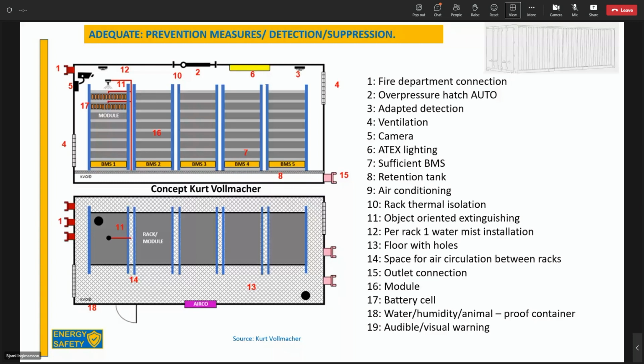The presentations may be available afterwards, but there's a fire department connection and overpressure valves - if gas is accumulating before an explosion, the overpressure valves will open. There's also the right detection, because you need detection specific to the cell chemistry that has been used.